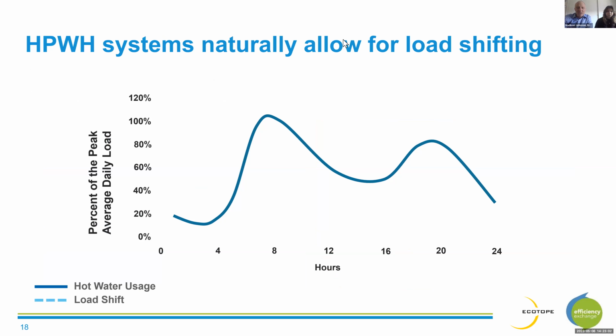So this is a picture of a typical hot water load shape for a multifamily building, at least pre-COVID. There's typically a large peak in the morning that's associated with people getting up and taking showers and making breakfast and coffee and so forth. Typically a low amount of demand in the middle of the day, because that's just the people that are staying home. And then a second peak in the evening around dinner time. And this is extremely inconvenient for the utility because that's exactly the shape of the utility peak demands. There's a morning peak in cold weather climates associated with morning warm up, people getting up and turning on their heating systems. And then there's an evening peak associated with cooling equipment coming on in the afternoon.